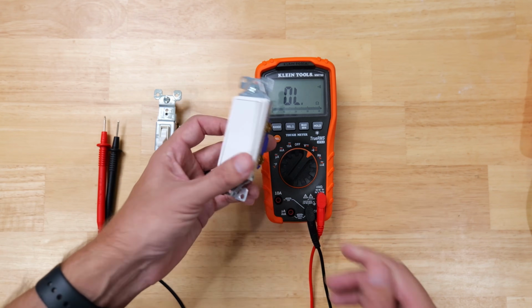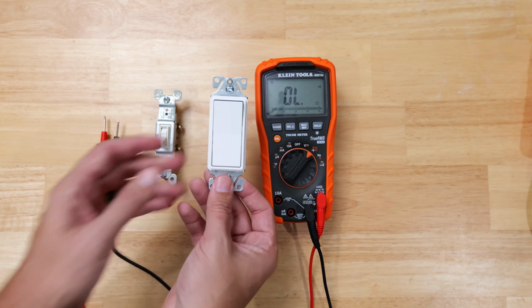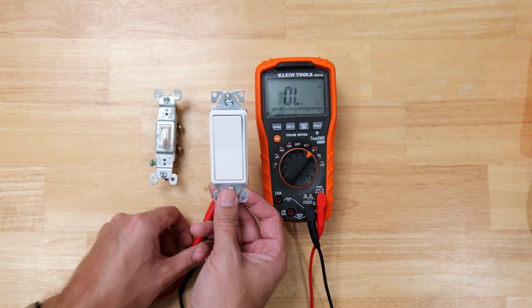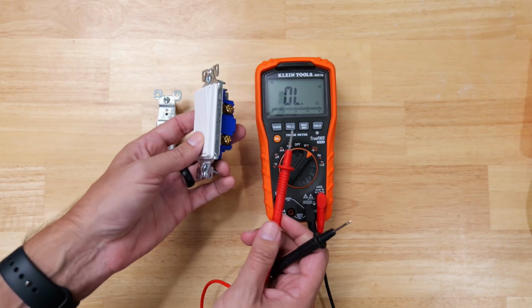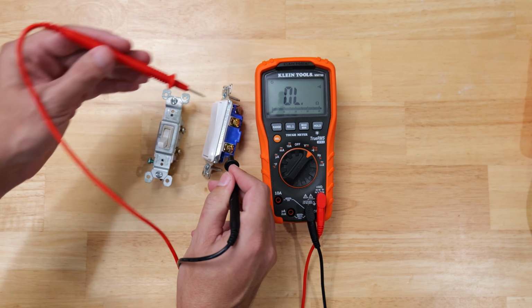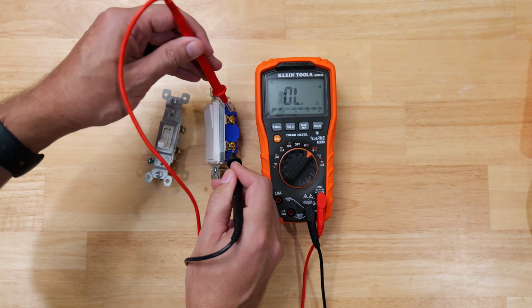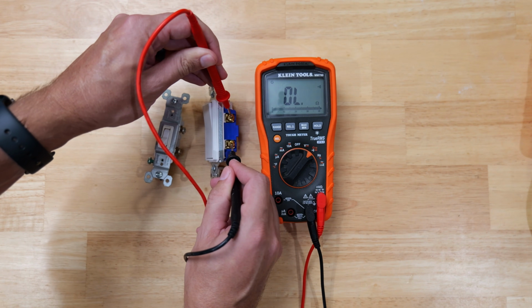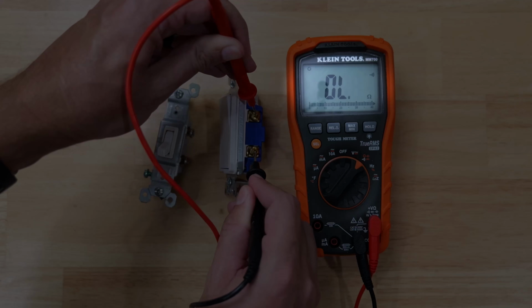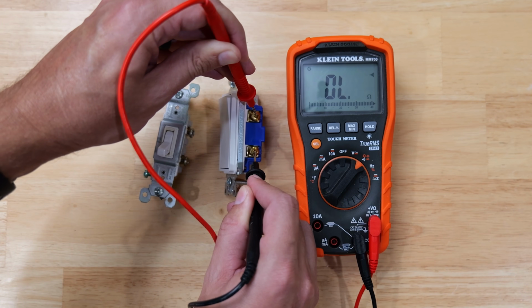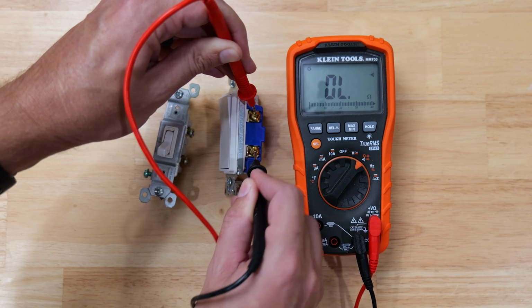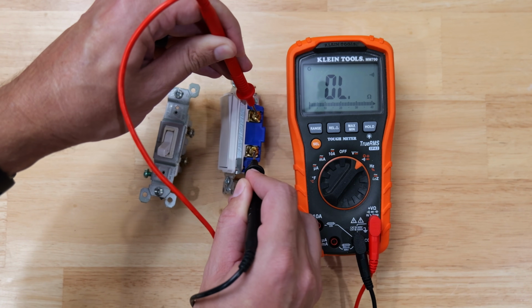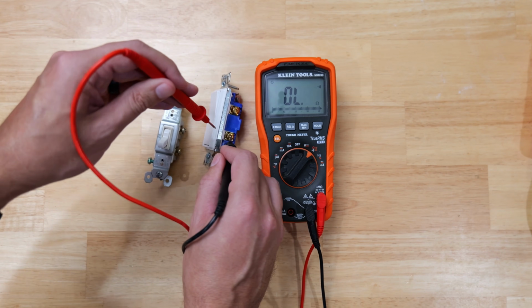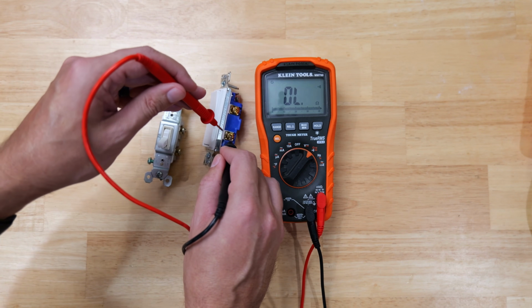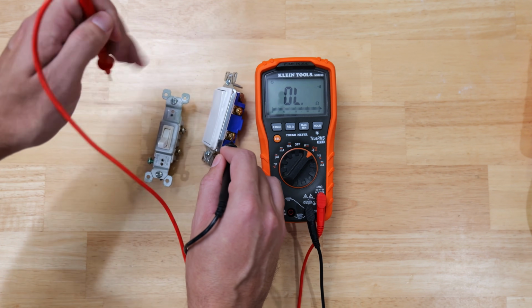Take our standard switch here—this is a Decora model, but it acts the same as a standard toggle switch—currently in the off position. If I take one probe and put it on the bottom terminal, and the second probe on the top terminal, it reads OL, meaning no reading, and it's not making that beeping noise. That tells us there's no connection, no continuity. Whereas when you flip a switch, that's what it does—this is basically a gatekeeper that takes current from one side and puts it to the other.